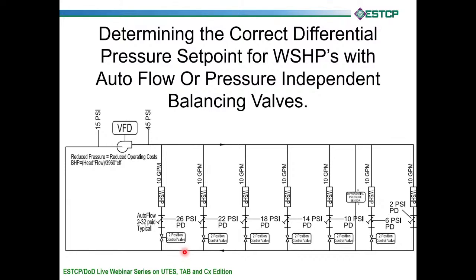Most of the time on water source heat pumps, you end up with a two-position control valve because we don't need it to be modulating. We just need it to be on or off. Another thing designers do a lot of times on water source heat pumps is they install these things called auto flow balancing valves, or sometimes they might specify a pressure-independent balancing valve. Both of those are really good ways to balance water flow on a water source heat pump job, because when we need the water source heat pump, the control valve opens up, and in our system here, each of these water source heat pumps need 10 GPM, and this auto flow, you would order it for 10 GPM, and it just flows 10 GPM.